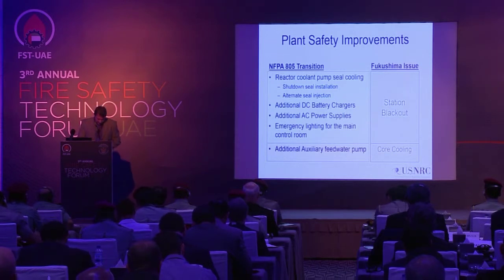So due to the NTTF recommendations, or Near-Term Task Force recommendations, and subsequent NRC orders, several enhancements resulting from the lessons learned during the events of Fukushima Daiichi are currently underway. Some of the modifications that were previously identified during NFPA 805 transitions intersect with the modifications being proposed to address Fukushima concerns, particularly in regard to mitigating strategies for beyond design basis external events. So that's that view graph here. You can see this is a simplified diagram, but the point is there's considerable intersection. And many licensees, or utilities, we call them licensees, are currently in the process of making the modifications for NFPA 805 that in retrospect will help them with a station blackout, which is what happened at Fukushima.